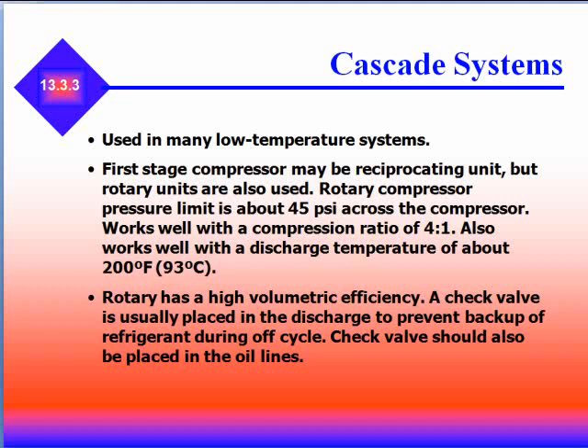Cascade systems are used in many low temperature systems. The first-stage compressor may be a reciprocating unit — rotary units are also used. Rotary compressors are pressure-limited to about 45 PSI across the compressor and have a high volumetric efficiency. A check valve is usually placed in the discharge to prevent backup of refrigerant during the off cycle, and check valves should also be placed in the oil lines.